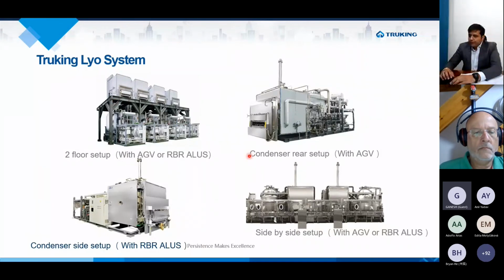These are the production scale freeze dryers, lyophilizers, which can adapt to the layout constraints of the user. For example, some facilities are greenfield, some are brownfield. Majorly in brownfield, we have the challenge of constrained layout sometimes. So the machine can adapt to different designs. For example, this is a two-floor setup with the chamber on the top, and the condenser and the refrigeration kit on the bottom. This can be with the standard orientation with the vertical condenser. We can put it on the side. We can put multiple lyophilizers side by side, again depending on the batch size and user requirement.